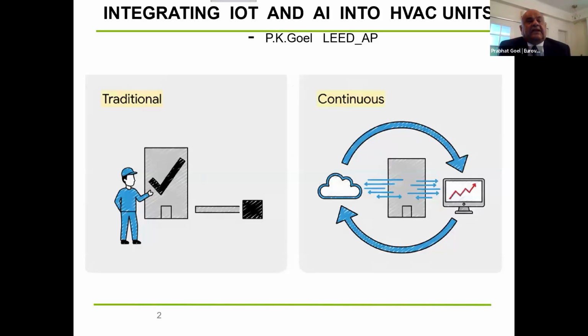So very well said that the COP or EER of the machine when we installed was 3.8 and 4.5, but that's just when it was installed. It loses a little bit of refrigerant. It even has a dirty filter or dirty condenser coil, and there it all goes. You come down to a smaller number, and there are millions of units out in the market, and we know the story how these units look after a couple of years of installation. And therefore, the amount of energy consumption in these particular things.